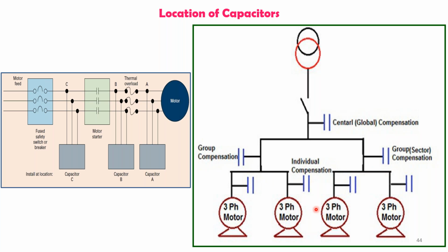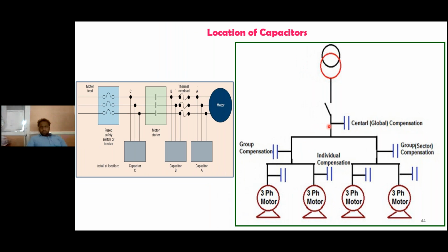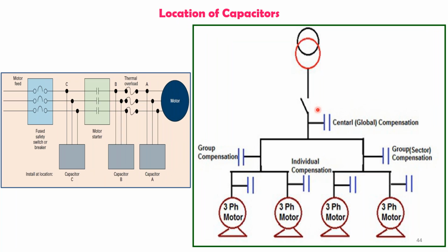If you are doing it like that, there are two benefits. Of course, a lot of benefits are there, but I just want to mention only two advantages. Number one, if you place the capacitor, the voltage distribution from the first point to the end point will be improved, so your motor will get almost the same voltage as the supply voltage. Number two, the distribution losses will also be reduced. Number three, the capacity of the APFC also gets reduced, because you are compensating the reactive power at the load itself. So the initial cost of the APFC will also be reduced, and your footprint and everything is going to be advantageous.